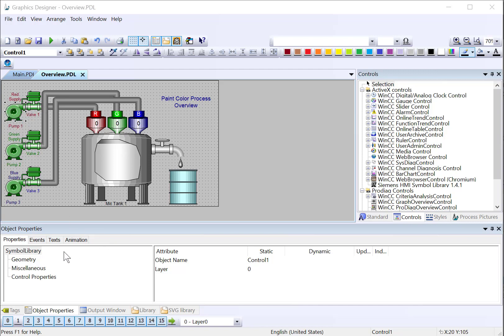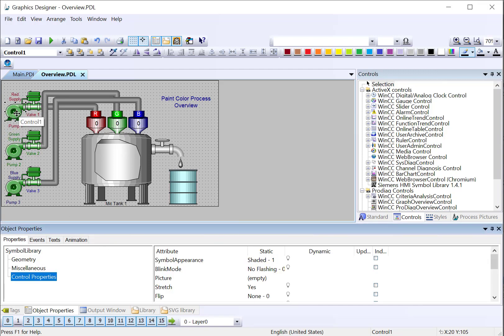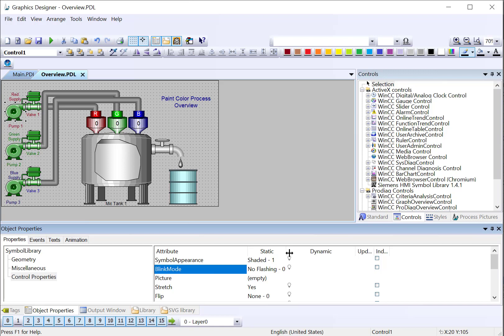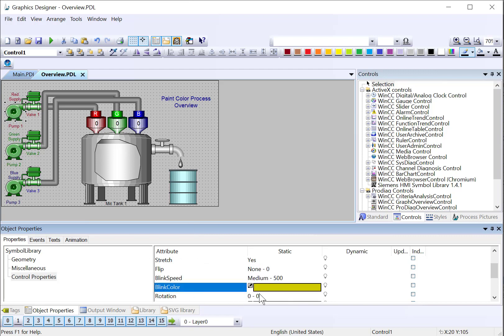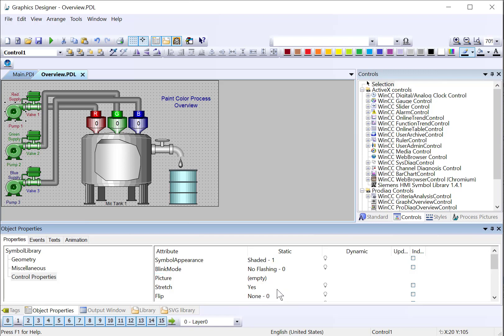So we'll start with the red pump. We want to turn the pump red if it's on, green if it's off, and we want it to flash yellow if it fails. We'll start with our blink mode. What we want to do is what we call shaded flashing. That just means that it will appear the same shaded color, and then it will flash between that and the blink color.